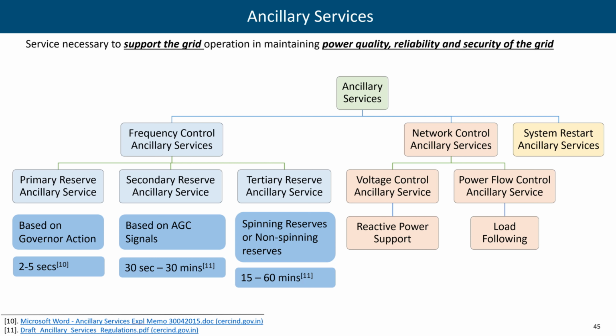In frequency control there are primary, secondary, and tertiary reserve ancillary services. Primary is based on governor action, and secondary is based on AGC. Tertiary is provided by spinning or non-spinning reserve, and these are slow acting. First, governor action comes into picture, and it can respond very quickly, within 2 to 5 seconds.